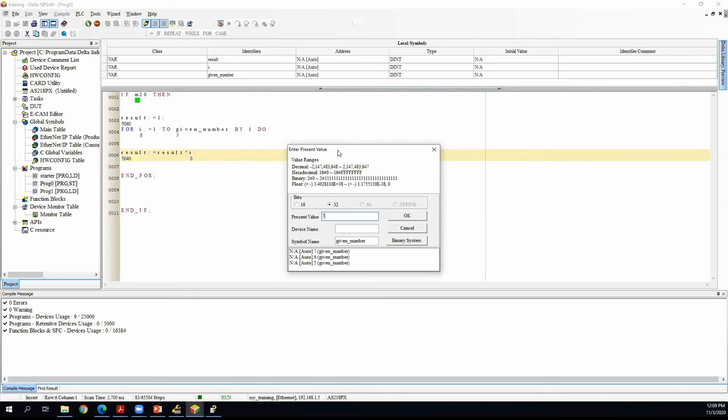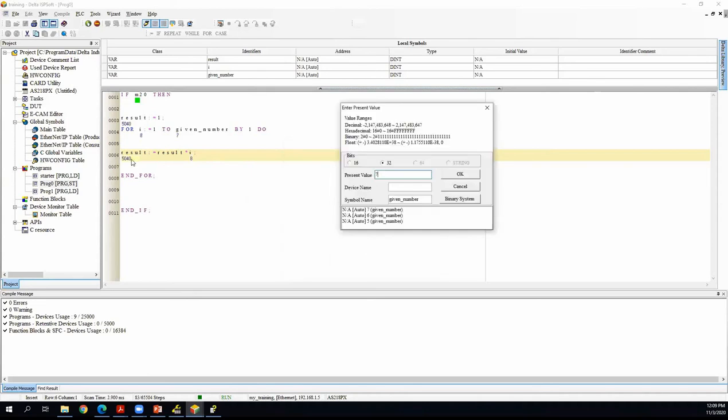So what I want to show afterwards, so you can see the result. Here at the bottom, you can see the scan time, right? So it is right now 2.8 milliseconds. And let's calculate 100. Then the scan time has already increased to 3.3 milliseconds.